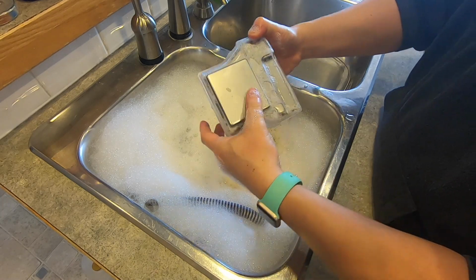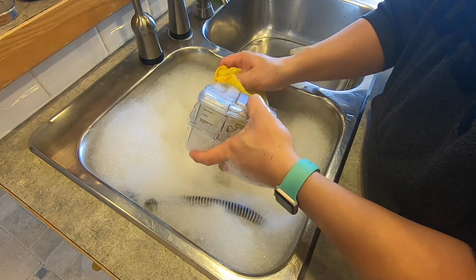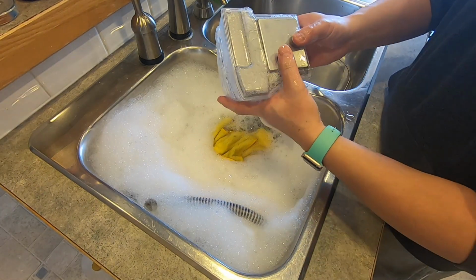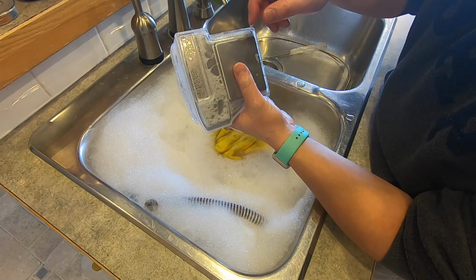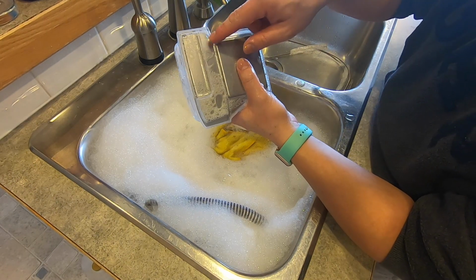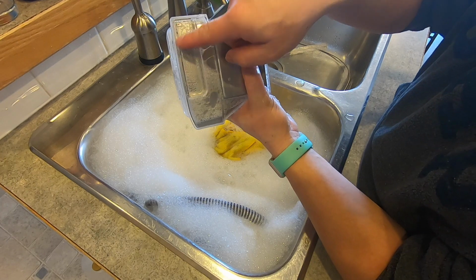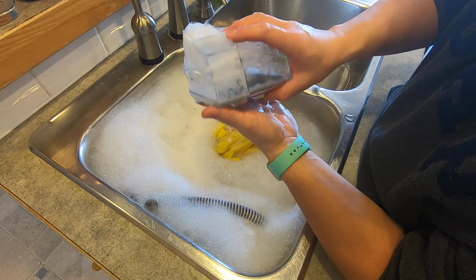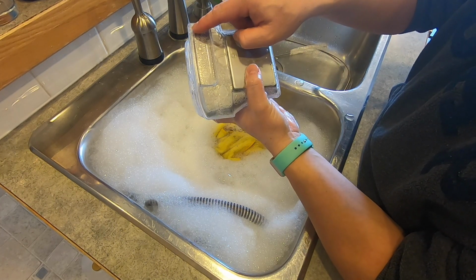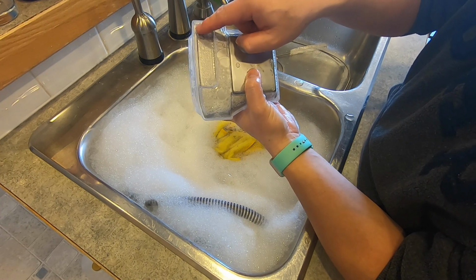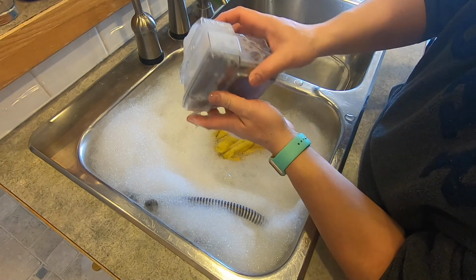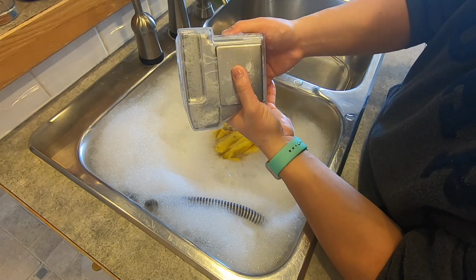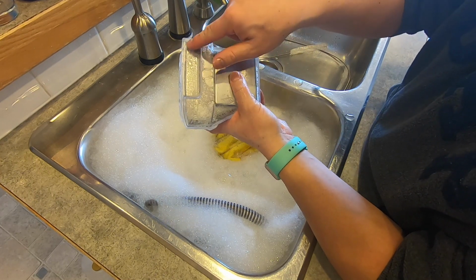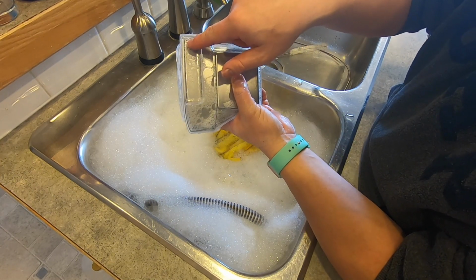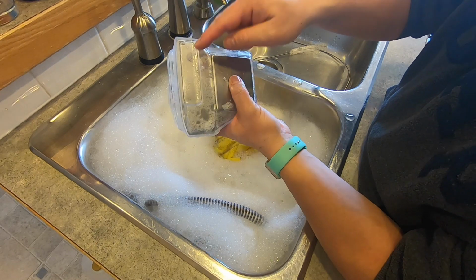Now, there is one thing I want to call out on the ResMed reservoirs that I haven't seen on other brands of CPAPs: this reservoir actually has a vent hole for the heating plate on the bottom of the reservoir. This hole, I believe, is a pressure relief hole, because as you heat the bottom of this reservoir, the air expands on the bottom side, and that just allows it to equalize the pressure. It doesn't pass through to the inside, it's just the outside.